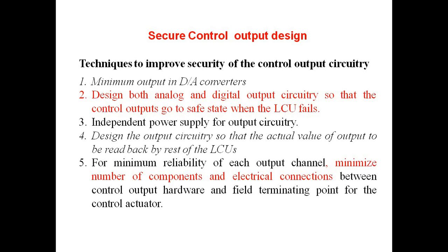First point, minimum output in digital and analog converters. Design both analog and digital output circuitry so that the control outputs go to a safe state when the LCU fails. Use an independent power supply for the output circuitry. Design the output circuitry so that the actual value of the output can be read back by the LCU.